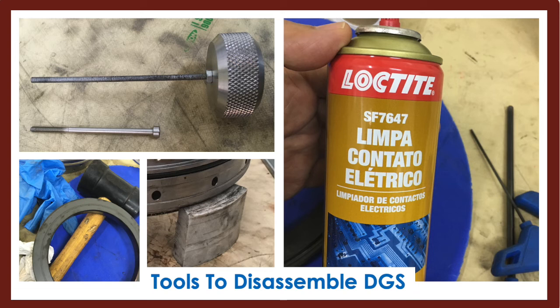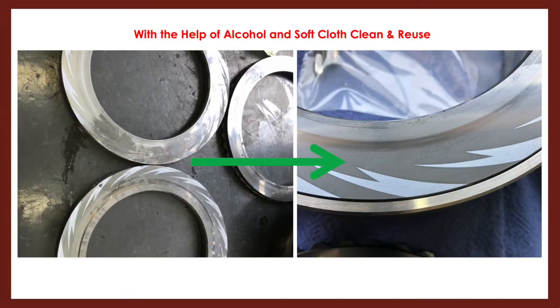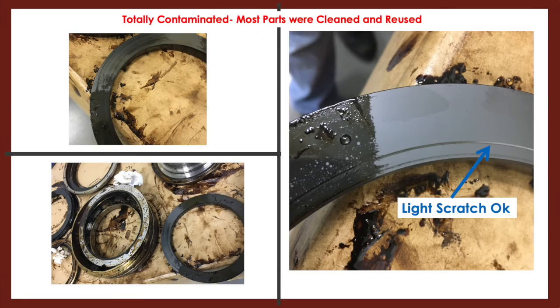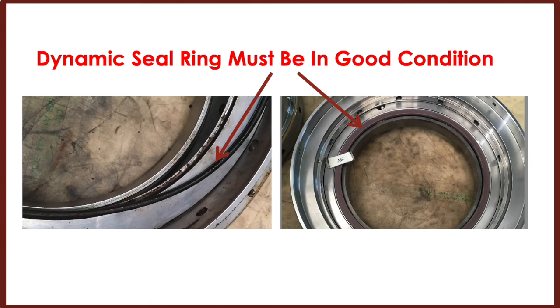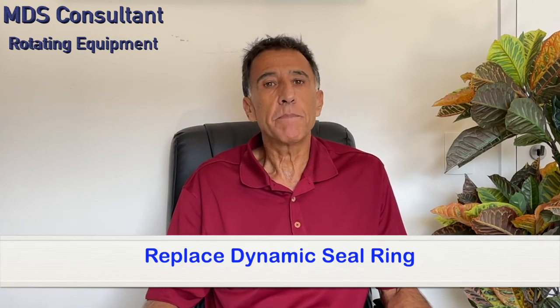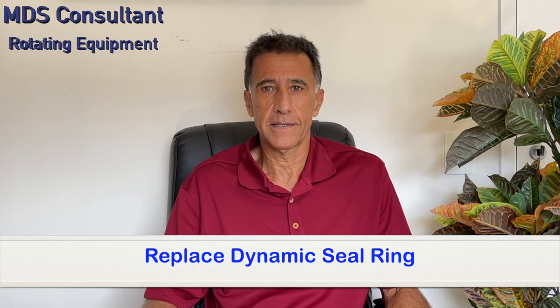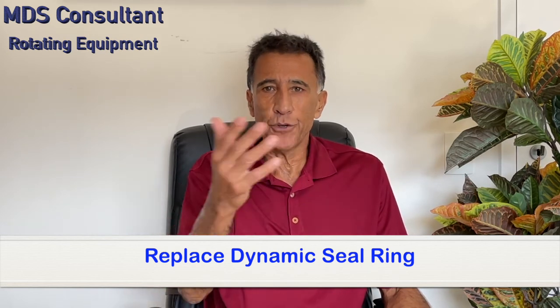There is no magic to it. You'll need some cleaning liquid like alcohol or electronic instrument cleaner to clean all the parts and put them back together. In most cases, you wouldn't need to replace anything. I wouldn't worry about a few light scratches on the sealing faces. Only deep cracks are of concern. The only part you need to be really careful about is the dynamic seal ring. And even that would need an eagle eye or an experienced person to decide if it's usable or not. Or just to be on the safe side, buy a spare dynamic seal ring and just replace it regardless. And put the seal back together and off you go.